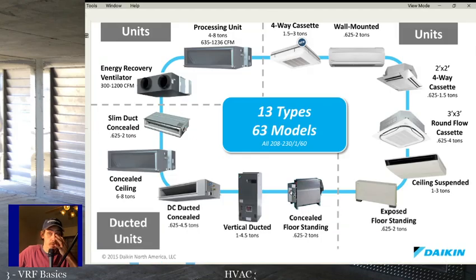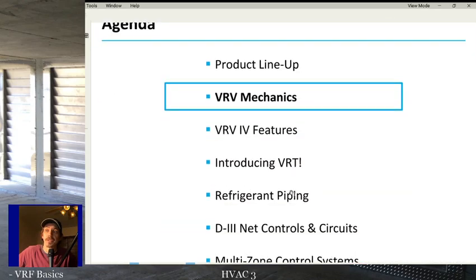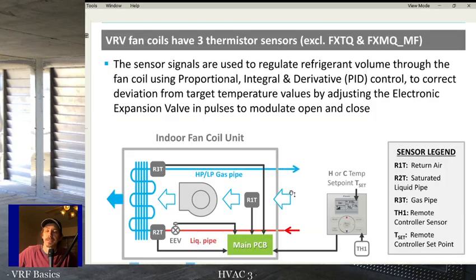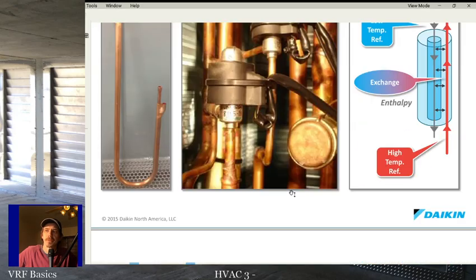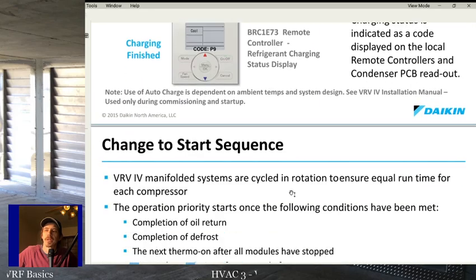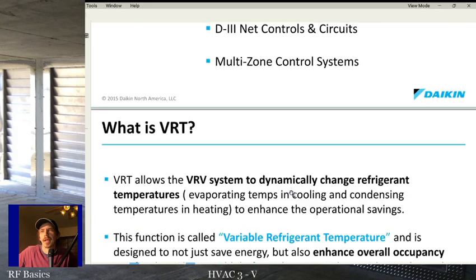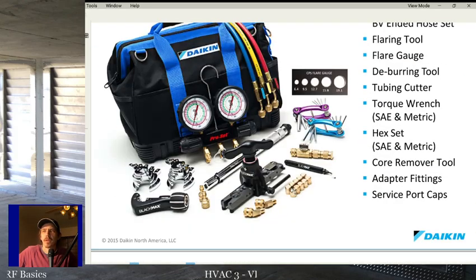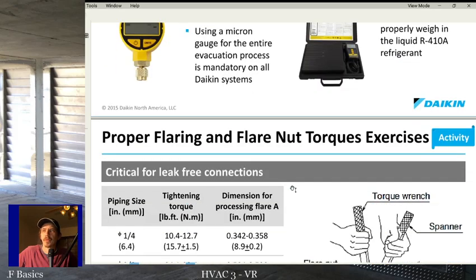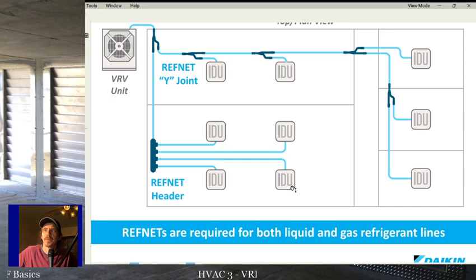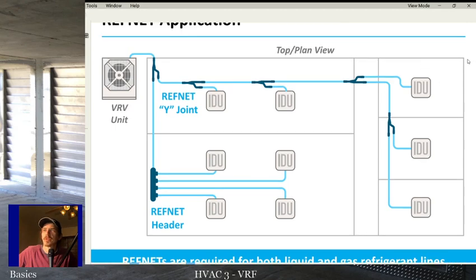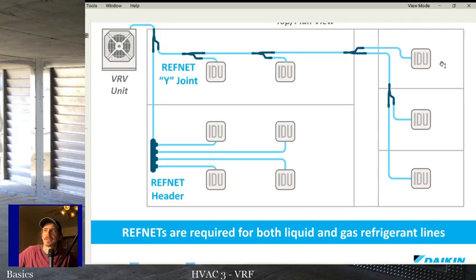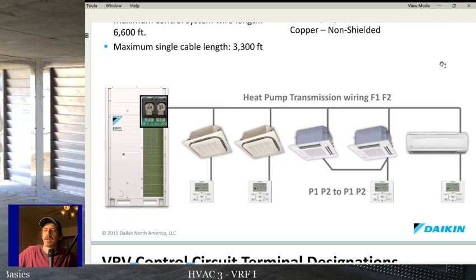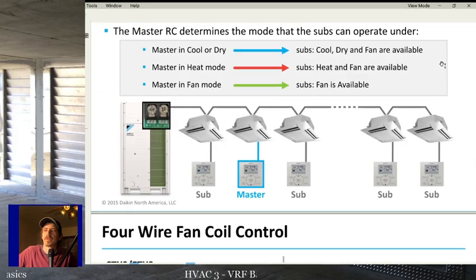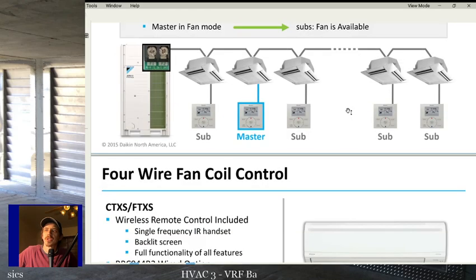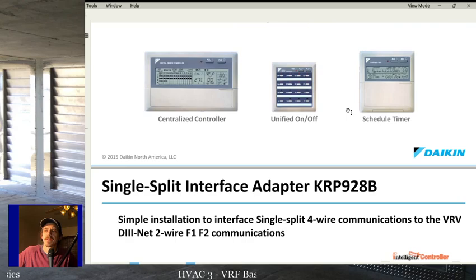Now, to control that, you're going to need a few extra things than you're going to need in a standard HVAC system. So let me see, I probably should have pulled up this diagram first because I knew I was going to go that route. But anyway, instead of 2 lines, you're going to have 3 lines coming out of the outdoor unit. And it's actually really simple if you think about it, if you understand a heat pump system pretty well. I know they're showing a heat pump. Where's the heat recovery diagram? All it really is, you're running the discharge line out, the liquid line out, and the suction line out.